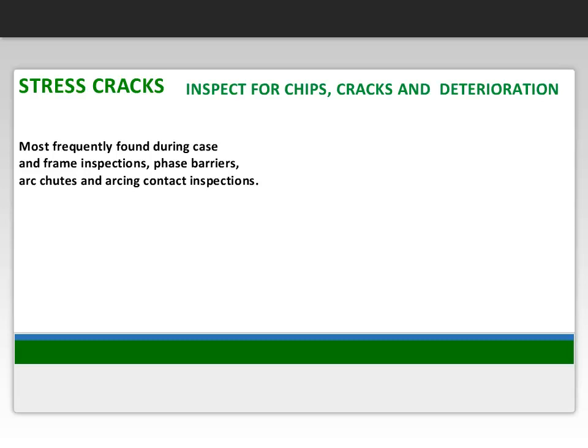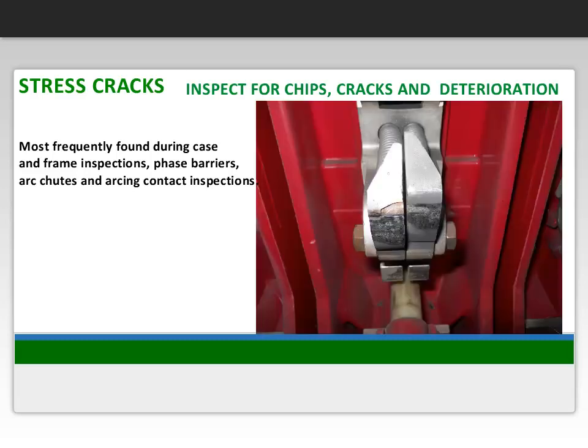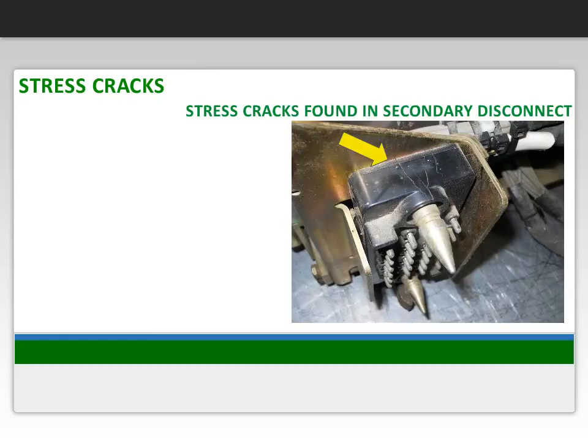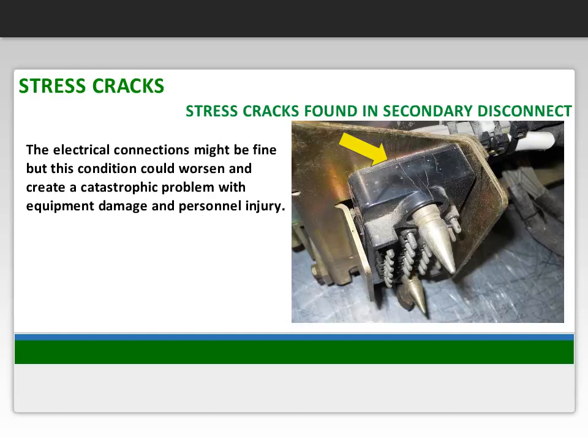Fatigue of components can occur over time, creating cracks, especially with insulated parts. In the section on arcing contacts, it says inspect for cracks, chips, and pitting. This photo shows a combination of these aspects, including deterioration and contact erosion. Notice the cracks on this secondary contact block. The electrical connections might be fine, but this condition could worsen and create a catastrophic problem with equipment damage and personnel injury. Let's test your inspection prowess.